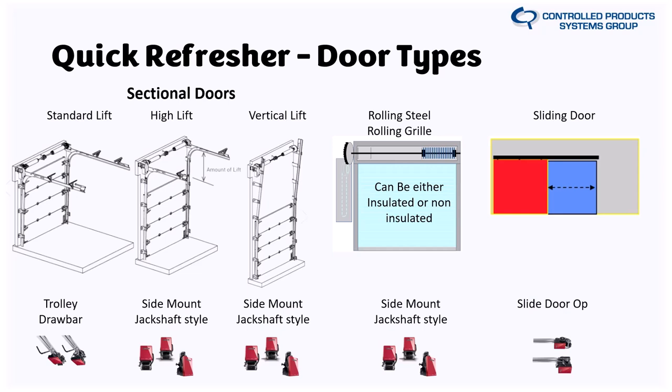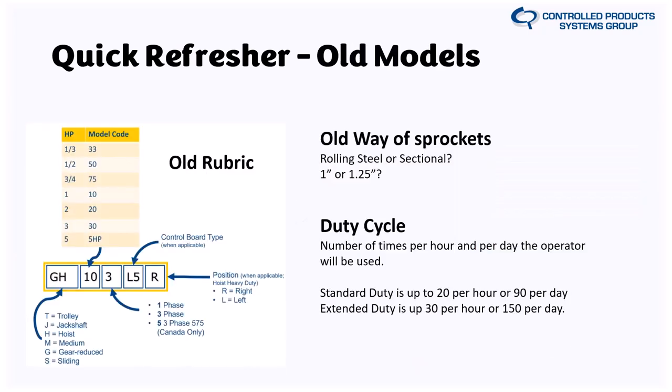For high lift, vertical lift, rolling steel, and grills, this is where we previously used a J, H, GH, JD, or similar rotational jackshaft configuration. As a quick refresher on old nomenclature: the prefix indicated the model type (trolley, jackshaft, gear-reduced hoist, or regular hoist). The next two digits were the horsepower indicator — 50 was half horsepower, 75 was three-quarter, 10 was one horsepower. The following character indicated single phase, three phase, or 575V for Canadian market, with dual voltage selectable at the control board.